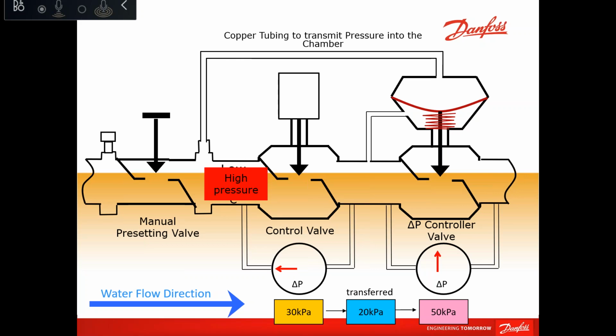So it is not really something dangerous to deal with, but it will be dangerous in case it reaches the pump. That's why you have the air vent, manual air vent or automatic air vent, to clear that air from your system. The PICV is not a really big deal.